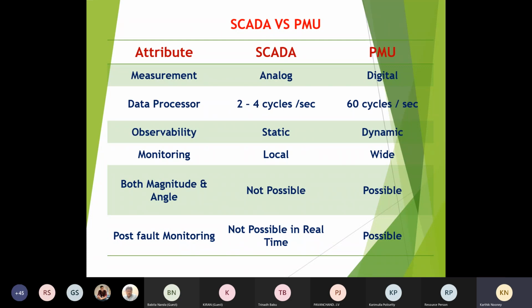But PMU, with whatever I have said, WAMS, wide area monitoring system, by the installation of these PMUs, it can monitor some heavy distances of the transmission networks also. In magnitude and phase angle with SCADA it is not possible, but with PMU it is possible. And in post fault monitoring, SCADA will only give you the particular location and it will switch off, but PMUs will analyze the data with the help of, I will show you now the diagram of PMU, how sophisticated that PMU is. But the PMU was invented in the 1980s itself.